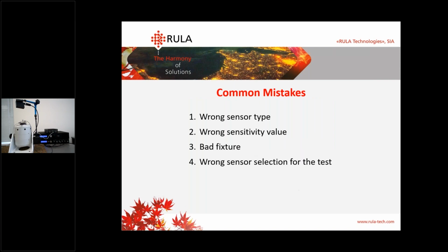And now let's talk about the common mistakes during the sensor setup in our software. First of all, you need to check that in your channel settings you have correct sensor types. For example, you have 3 IEPE sensors. They are connected, but in software you have linear sensor type. It's a huge error, and you can damage your equipment in that way, because the system will get a response, but it will be much lower, and we can try to control with these low values. In that case, we can have errors, emergency stops, so you need to check sensor types. After that, you need to check the sensitivity. You need to place it in the units, and its value must be from the sensor's passport.